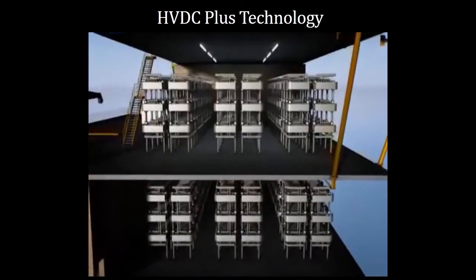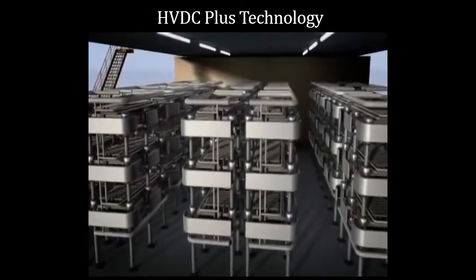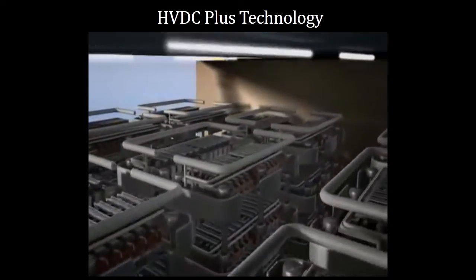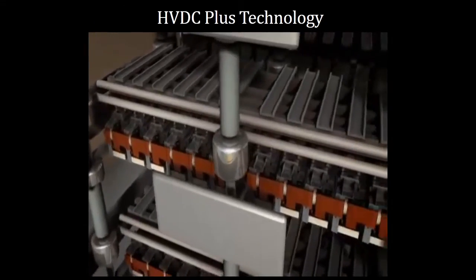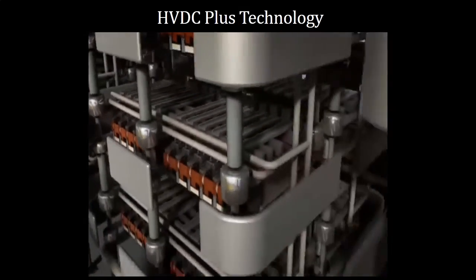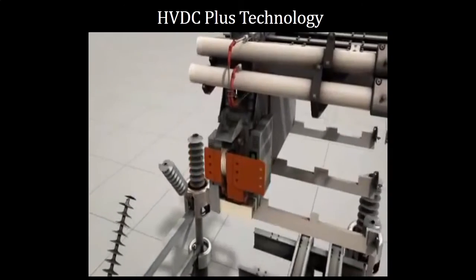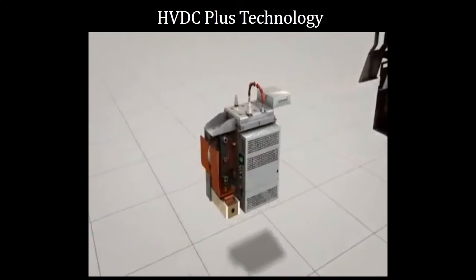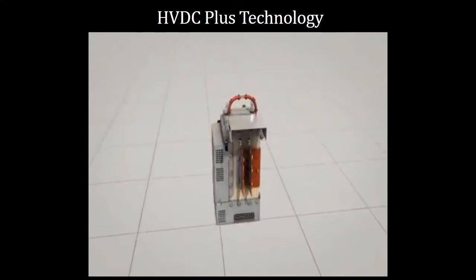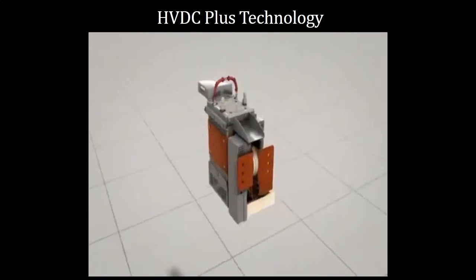The converter of HVDC Plus consists of three phase units. Each phase unit comprises two converter arms, each with a converter module and a converter reactor. Each converter module houses a large number of power modules connected in series, up to 200 or even more. Each power module contains two IGBTs as the switching elements, a DC storage capacitor, and the power module electronics.